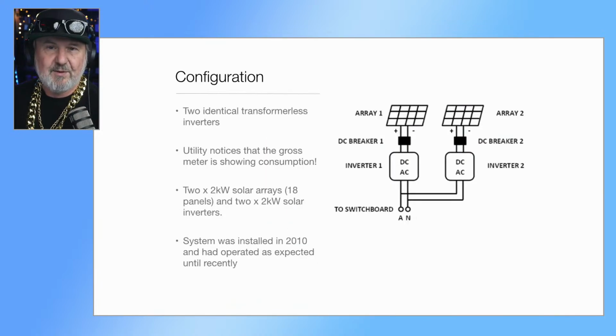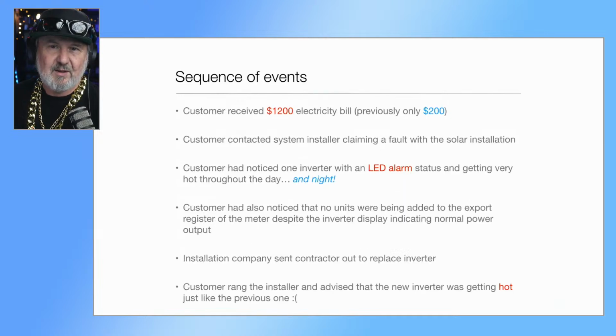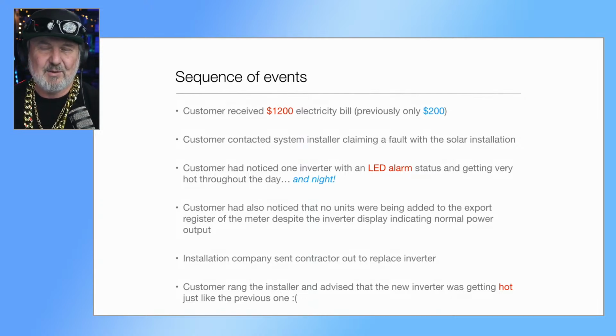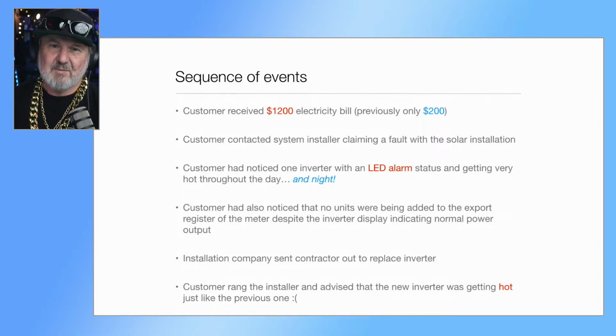I'll be fairly brief on this one, but the problem really was that even though the system configuration was fine, what they found was that the inverter was hot night and day, and for some reason the customer didn't think this was a big problem initially. They did contact the installation company who replaced the inverter, but they replaced it at the end of the day when the sun was gone down, so they couldn't test it. Next day, same problem. Inverter was still hot.